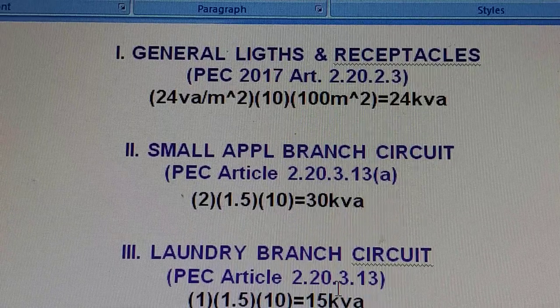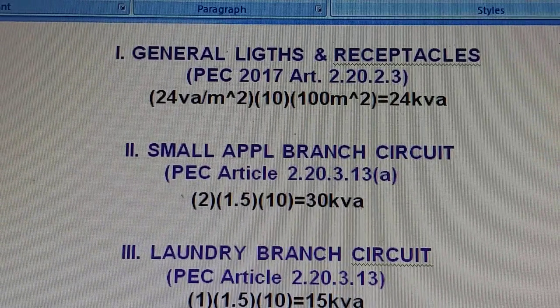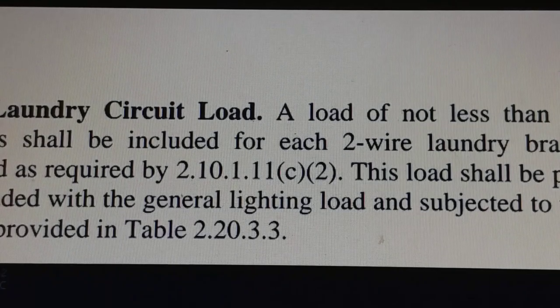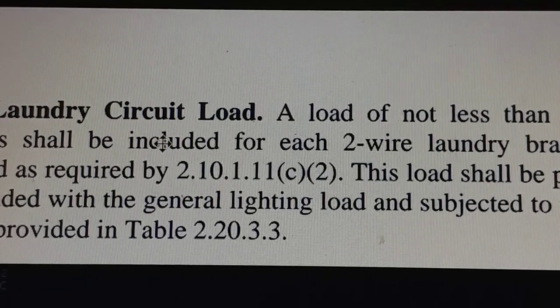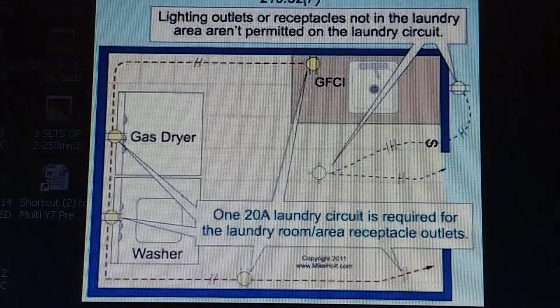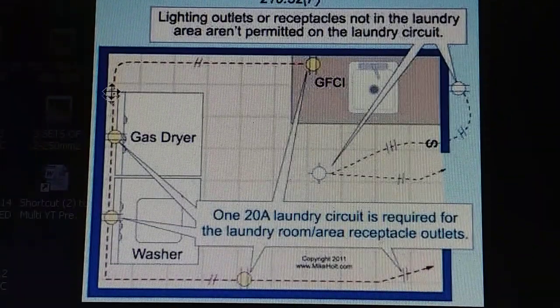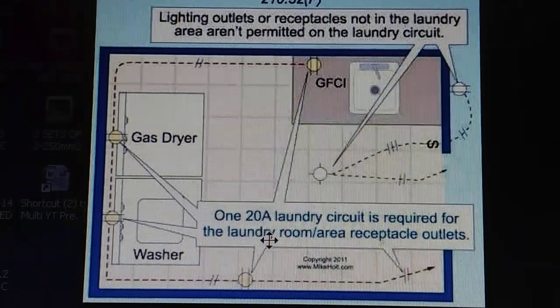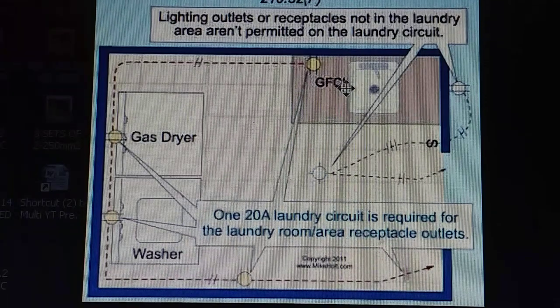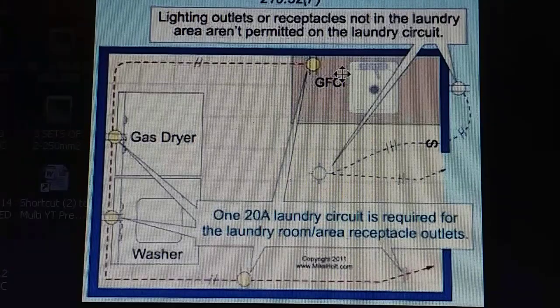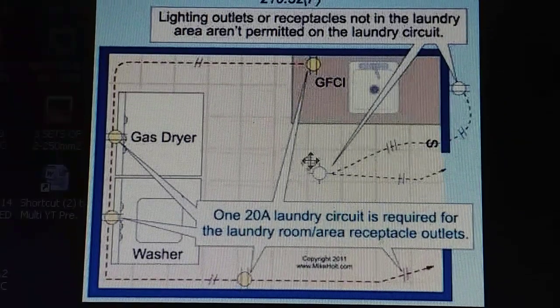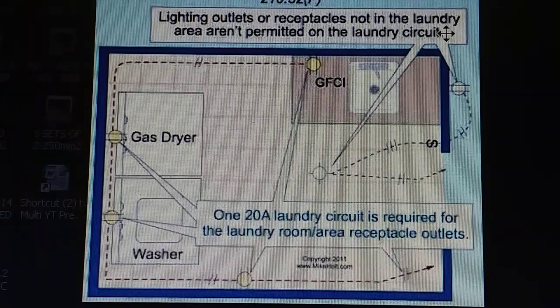For the laundry branch circuit, we only have one here. The article states that not less than 1500 volt-amperes shall be included for each two-wire laundry branch circuit, so we need only one two-wire laundry branch circuit. In the laundry layout, we have a 20-amp laundry circuit with a GFCI receptacle for the washer. According to the code, you must not connect any light circuit to this laundry branch circuit — this is not allowed.